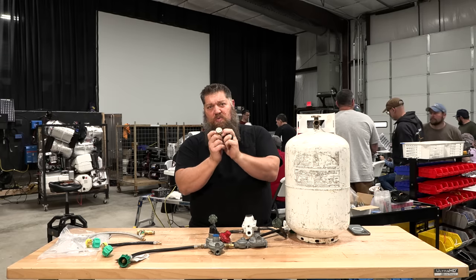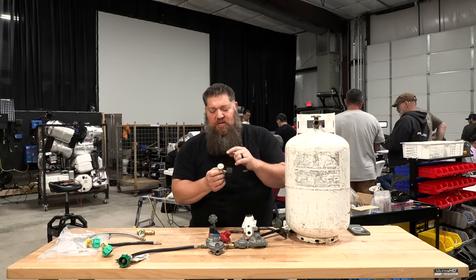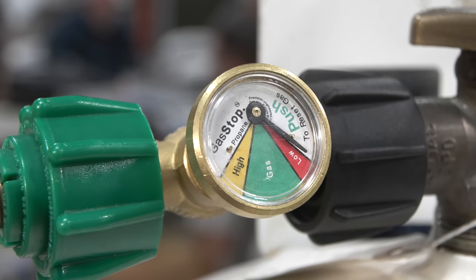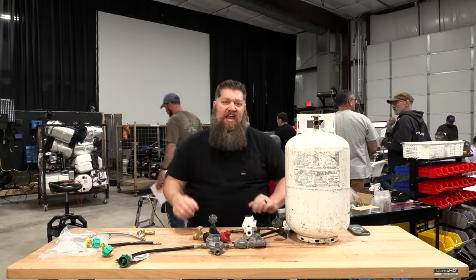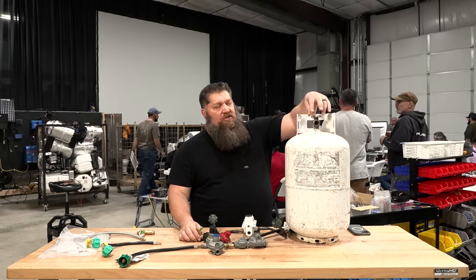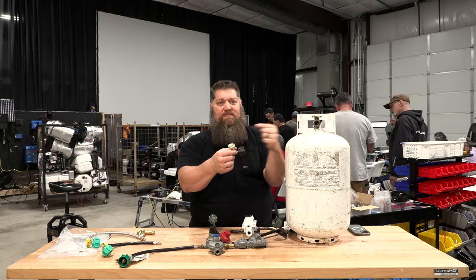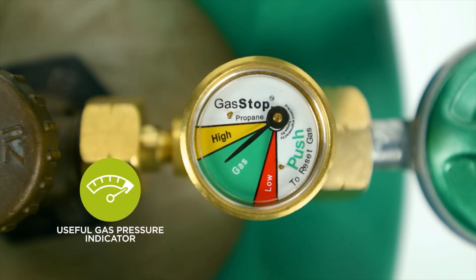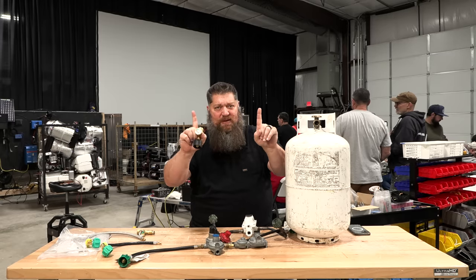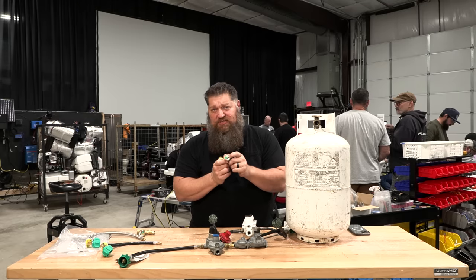What you can do with the Gas Stop is just perform a leak test. On the Gas Stop itself, it does have a small dial. What you can do is charge the system. All you have to do is turn off everything that calls for propane — no propane appliances. Charge the system by opening up your valve and then shutting it off. The service valve is now closed; the system is charged. You're going to see an indicator of where this is — take a picture of that. Walk away and come back in about five minutes. Take another picture. The reason I say take pictures is because when you take pictures, you can easily compare the two and see if the indicator has changed positions.